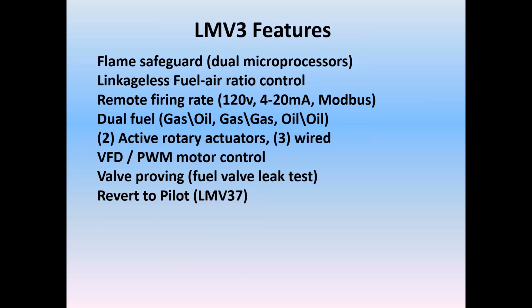LMV37 can do a revert to pilot. This is an awesome feature on small burners, such that when the load is satisfied and the burner comes down to low fire, typically the pressure or temperature will continue to increase until you turn off on your limit setting. That causes a post-purge, a shutdown, and then a subsequent call for heat would cause another pre-purge, and then go back to low fire.